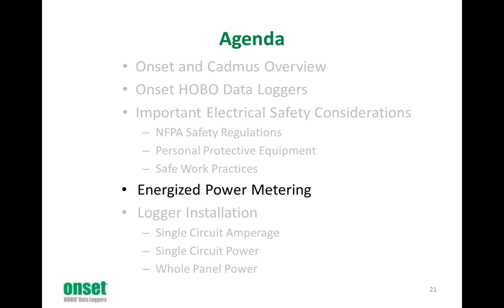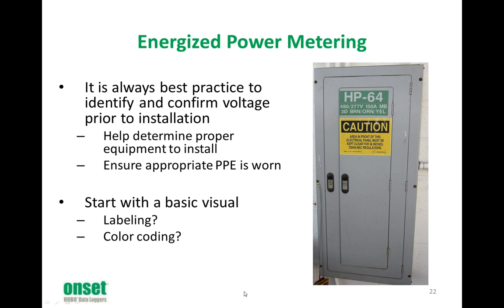And now we'll get into energized power metering. It is always best practice to identify and confirm the voltage prior to installation. This will help you determine the proper equipment you're going to install, and also help ensure that you're wearing the proper personal protective equipment. Start with a basic visual. Take a look at any labeling or color coding. On this panel here on the right, you can see that it's clearly labeled 480, 277 volts, and the color coding for that is brown, orange, yellow. So we know that we're going to be in the hazard risk category 2, so we'll need our full arc flash suit to open up that panel board.